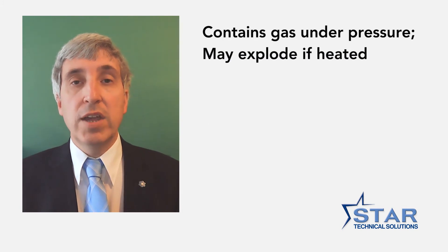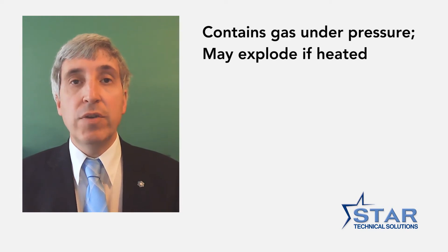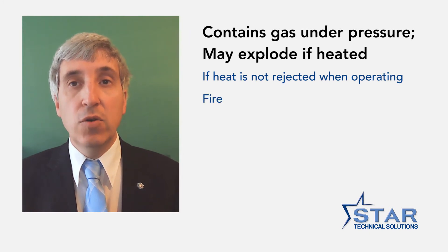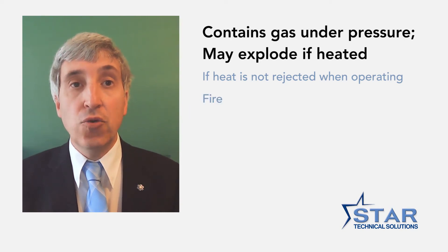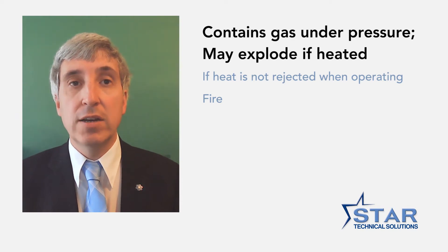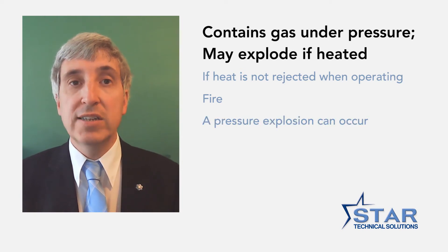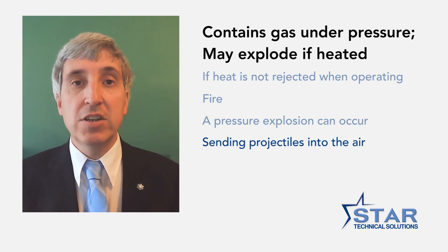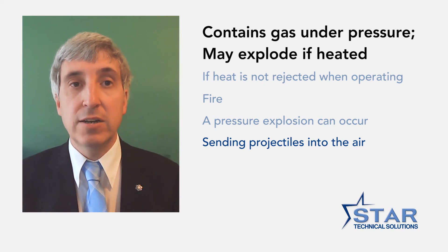The third hazard associated with ammonia is that it contains gas under pressure that may explode if heated. When ammonia is in a refrigeration system, its pressure will increase further by either not rejecting the heat it generates or in the event of a fire. As the liquid ammonia is heated, it is vaporised and its pressure increases. When the pressure in the refrigeration system increases beyond the refrigeration system's integral strength, components of the refrigeration system can rupture, exploding and sending parts of the system — including vessel and pipe components — and ammonia itself as projectiles which could harm people, damage the structure of a building, and result in flammable and toxic gas being present, which can form other hazards as discussed earlier.